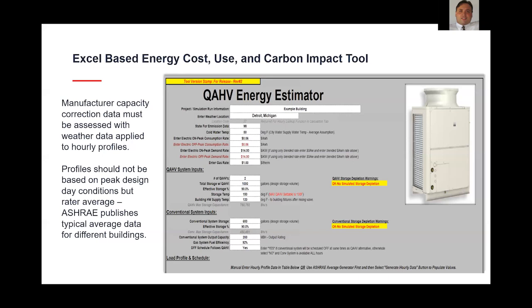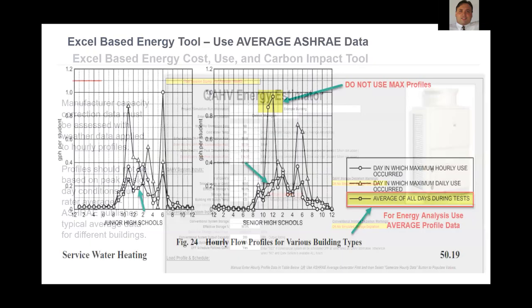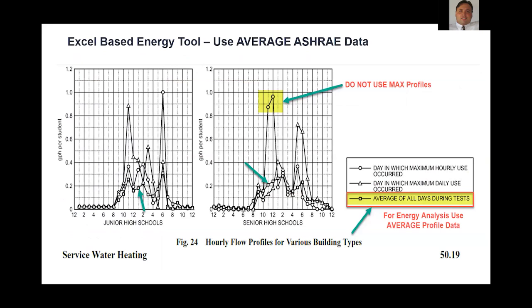It also includes EIA emission rates for multiple states. You can look at CO2 emission impacts. You can enter conventional system inputs, your CO2 heat pump water heater design. Obviously, this is based on Mitsubishi's gear. And then you can enter an ASHRAE average profile in the absence of knowing a specific hourly profile. And that's really key. And that's part of the challenge in assessing this.